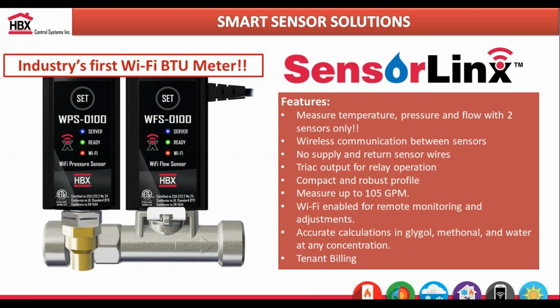In Europe, that's the go-to. A lot of the mechanical systems are very compact, with everything close together. But in the North American market, that's not the case. Your return and supply piping may be 20 to 30 feet away from each other. So typically, if you want to use other BTU meters, you're going to have to do some repiping, and unfortunately that's going to cost a lot of money, especially if you're doing retrofits.